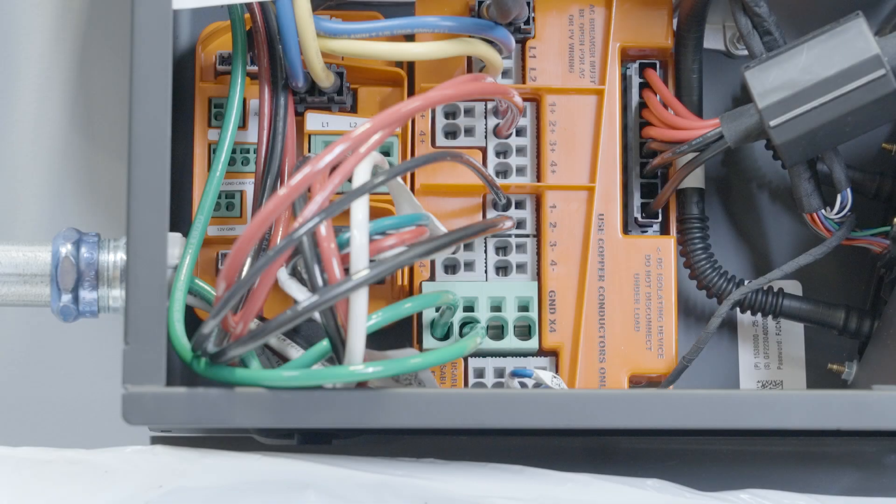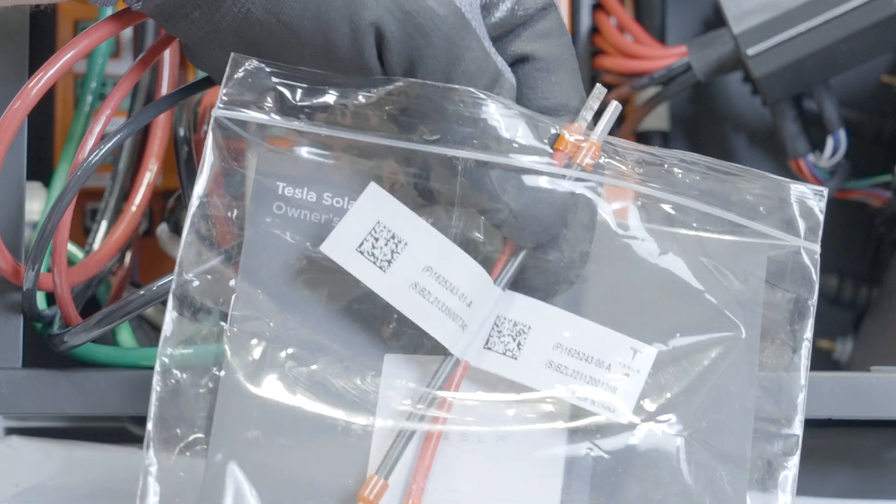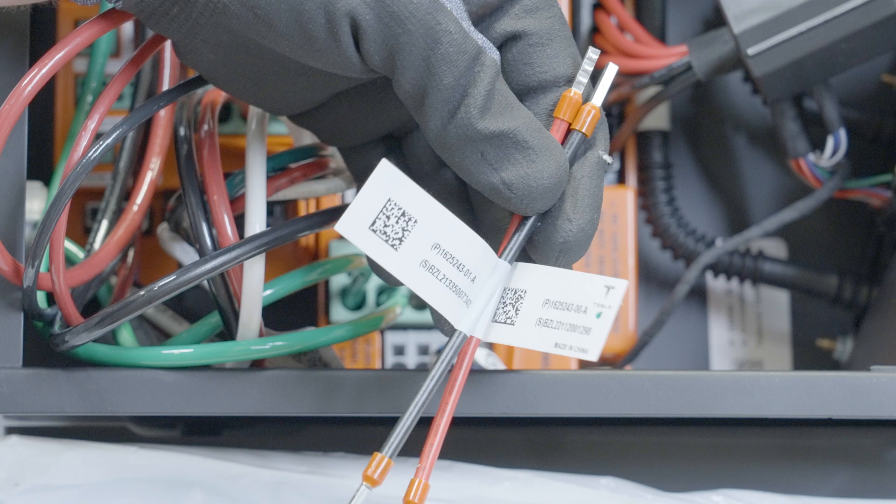If the current for a DC circuit exceeds the 13-amp rating of the terminals, DC conductors are then terminated on the left side, and jumpers are used to join the corresponding sets of terminals for a total allowable current of 26 amps for that circuit.